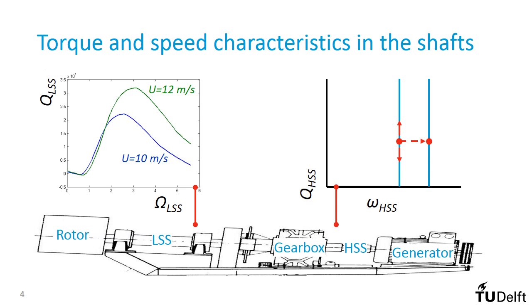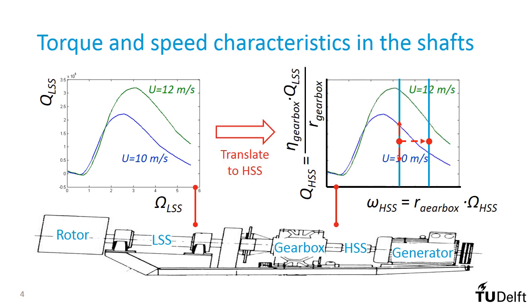Finally, we get to the crucial step. In the high-speed shaft we have looked into the direction of the generator. But what are the torque-speed characteristics if we look from the high-speed shaft into the direction of the rotor? In other words, what if we disconnect the high-speed shaft from the generator and connect it to the testing machine there? We can achieve these characteristics by using the gearbox properties. These tell us what happens to the torque and speed from the low-speed shaft when they are transferred to the high-speed shaft. Using these relations we can translate the torque-speed curve of the low-speed shaft to its equivalent in the high-speed shaft, as shown here.